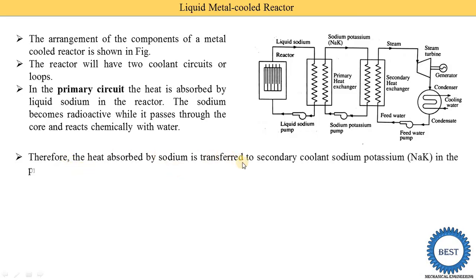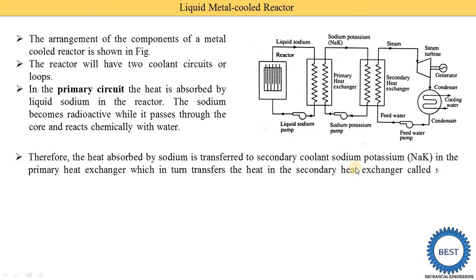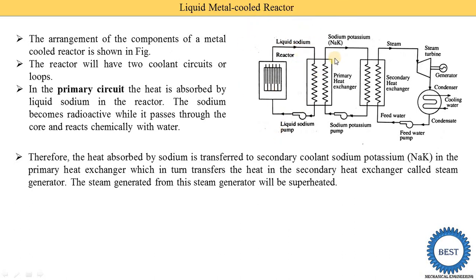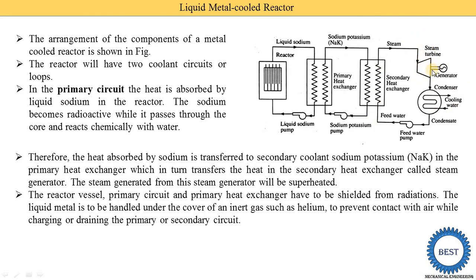The heat absorbed by sodium is transferred to the secondary coolant, sodium-potassium, in the primary heat exchanger. The sodium-potassium then supplies heat to the secondary heat exchanger, where it converts water into superheated steam. This steam drives the steam turbine to produce mechanical energy, which powers the generator. After condensation, the water is fed back through the feed water pump to the secondary heat exchanger, completing the cycle.